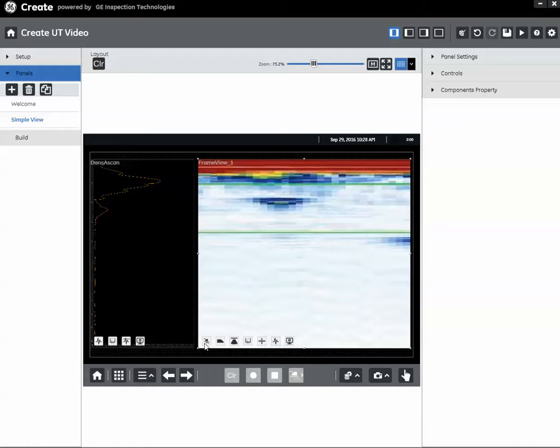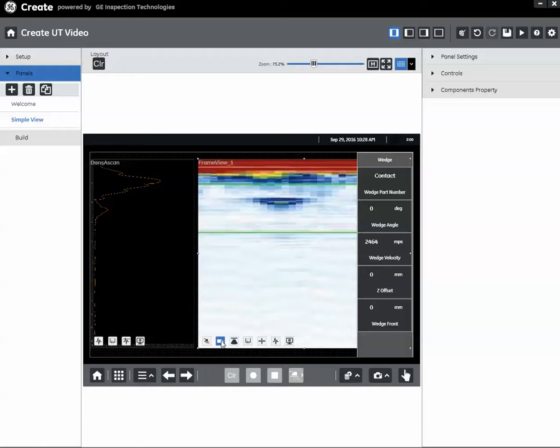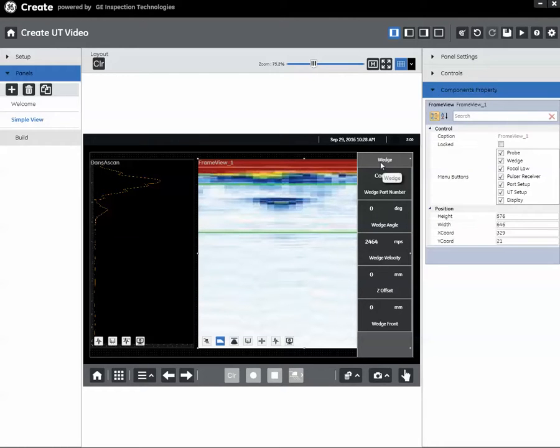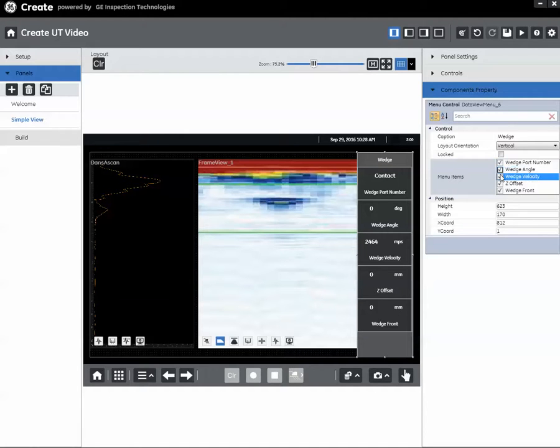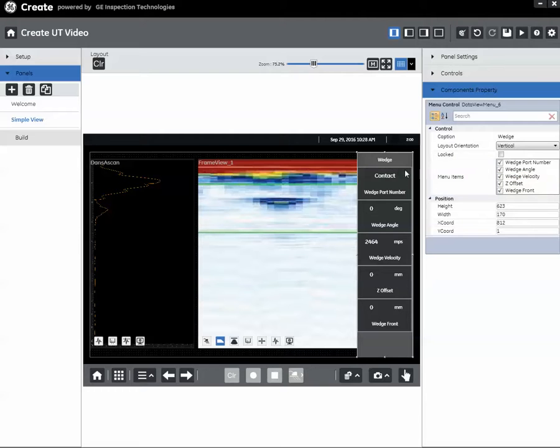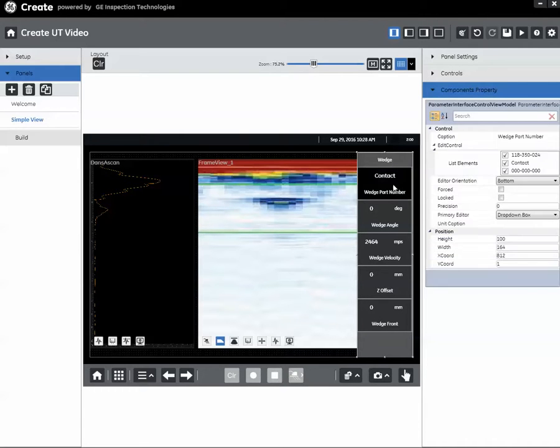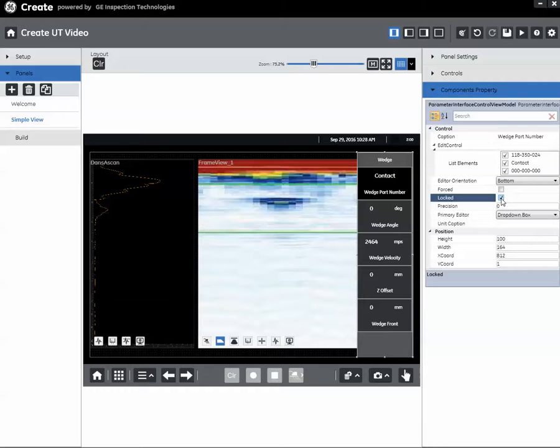You'll notice at the bottom of each one of the data views we have our menus. By clicking on the menu buttons I can open the menu. As we discussed before, if I select the entire menu I can choose which items are included or not included on the menu when the app runs on the instrument. If I select an individual control, I can lock that control. So that means it will appear on the menu on the instrument but the operator will not be able to change it.